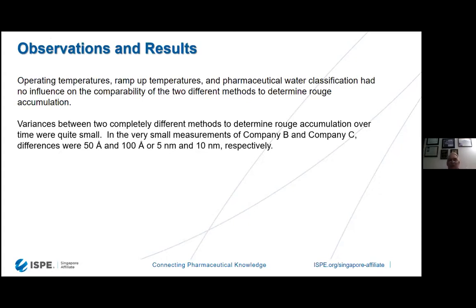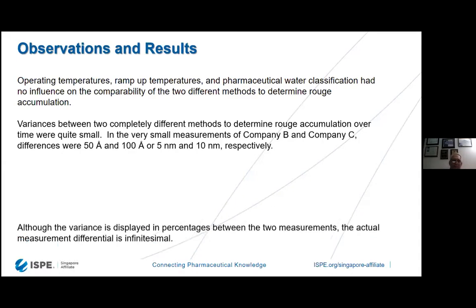And the rouge monitor, once it's installed, is not removed. You put the rouge monitor in the system and you leave it there. And any derouging or passivation you do in the future, you let the probe see all the data. Once you're done with the derouging passivation, you can reset the system back to 0 in order to start accumulating anew, but you don't want to disassemble the probes from the system.